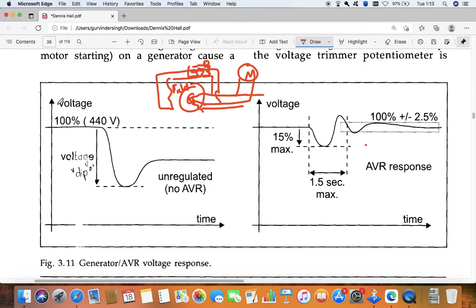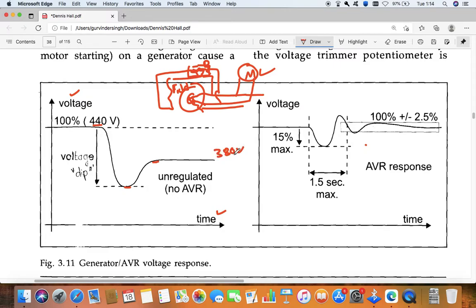So let's see with this diagram and graph. This is the voltage, and this is across the time. Now your generator rated voltage is 440 volt and it is 100%. So the generator is running at 440 volt. Suddenly the motor starts - when the motor starts, the voltage dips and then slowly it will try to come back. It will not reach - maybe it will reach 380 or 370 volt. So let's say it reaches 380 volt. So without AVR, if no AVR is there, there is a loss of voltage.